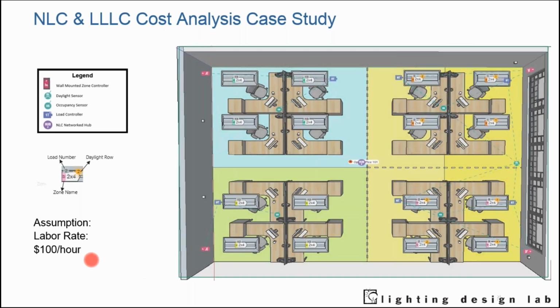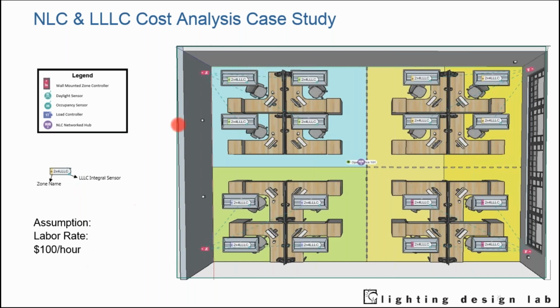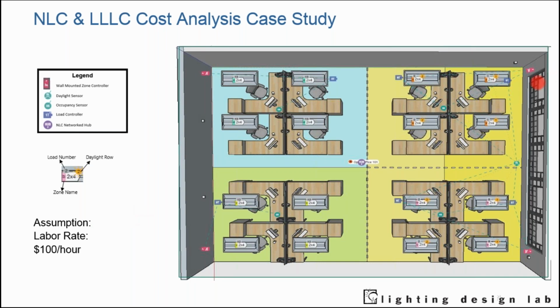We also have a luminaire level lighting control version of this space, where you don't see the motion sensor, you don't see the daylight sensor - you just see an LLLC fixture that has both. Wall stations remain there, the hub or gateway for the system remains there, but you even have less load controllers.